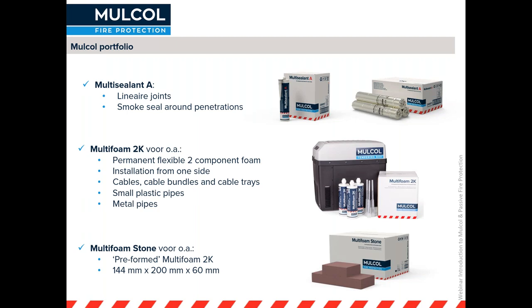The Multifoam 2K and the Multifoam Stone are two-component foams that remain flexible throughout their lifetime. The very nice thing about this is it can be installed from one side only, and especially the Multifoam 2K has a mixing tube nozzle, so it mixes together only when it comes out of the cartridge. You can reach very difficult areas that might otherwise be nearly impossible to reach. The other nice thing is that you can adapt your fire stopping penetrations afterwards. For example, if you've got different cables that need to go through the penetration, you can add cables and remove cables without having to redo the full opening.